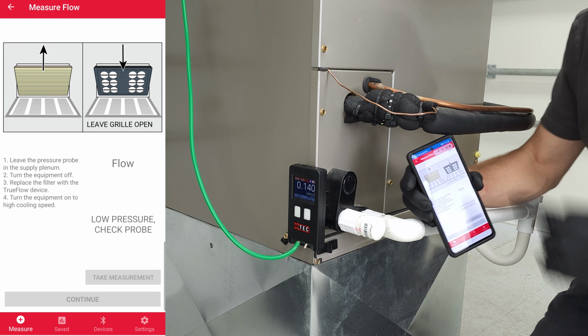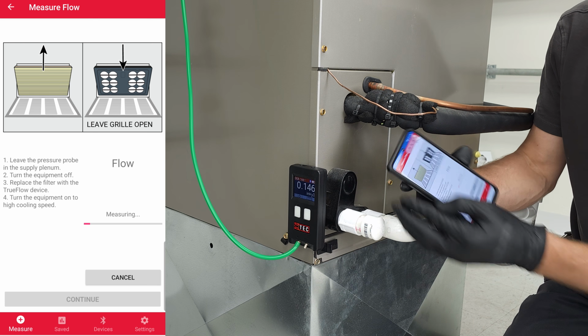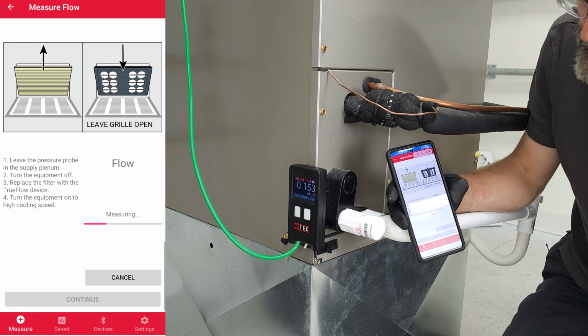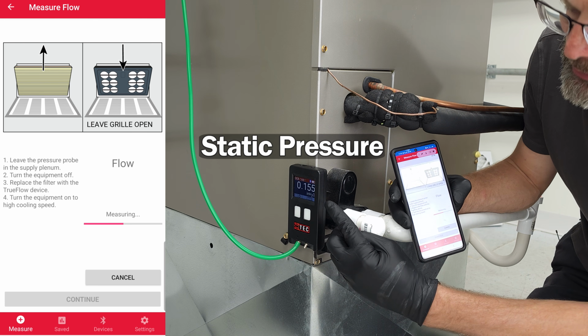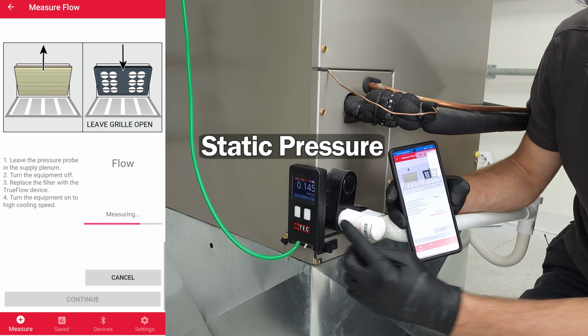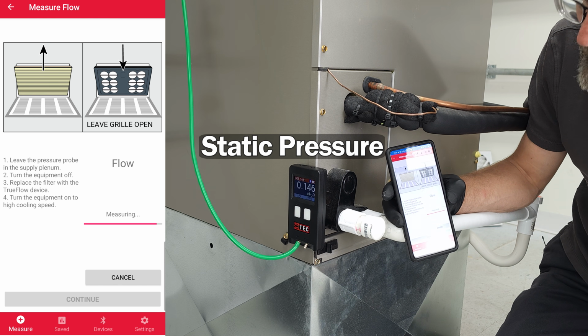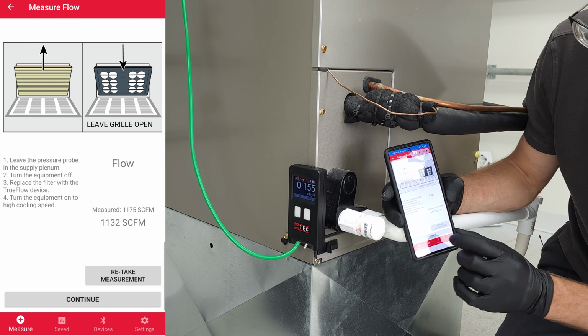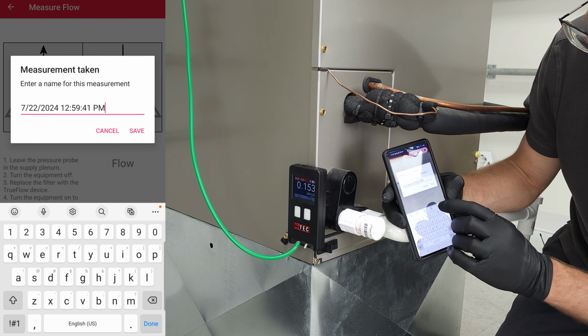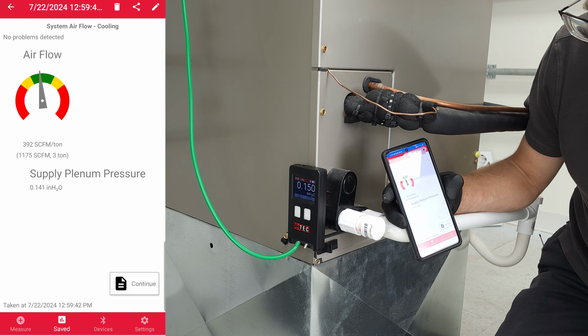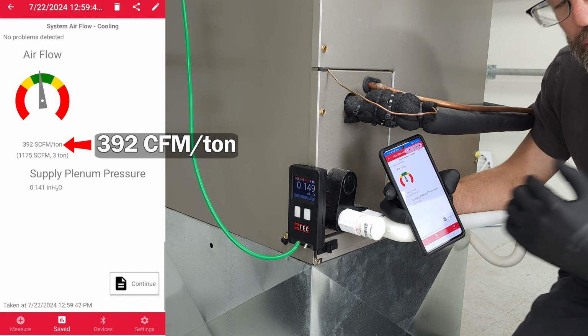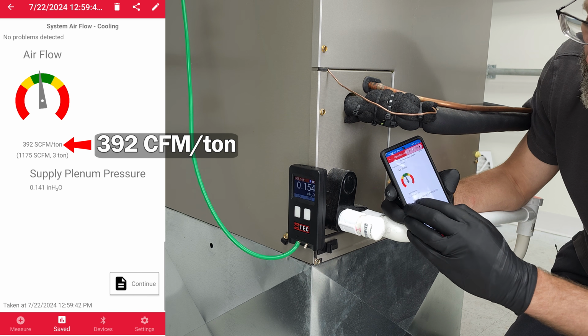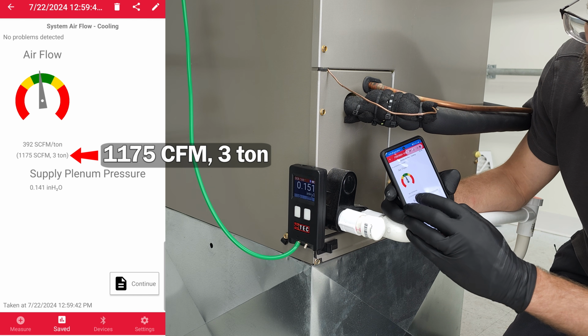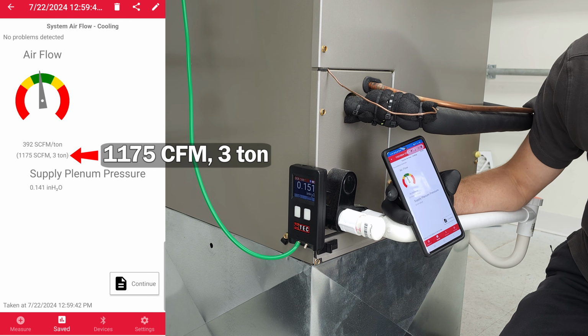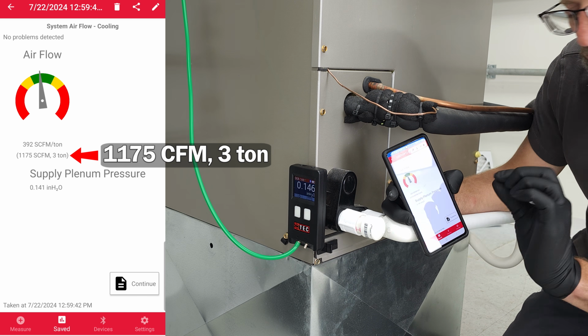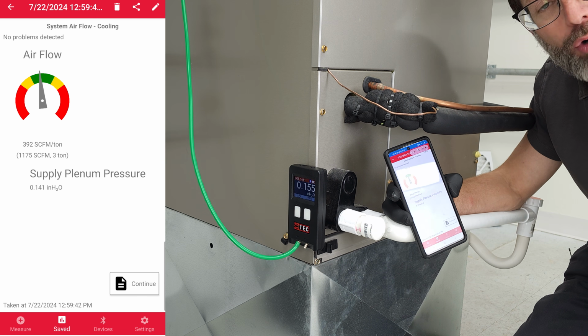Now we're going to switch out our filter with our TrueFlow grid. We're going to take our measurement now. So this static pressure measurement is a reference point in order to be able to measure our CFMs through this app. And so continue. We can save this. And it's saying that our airflow is 392 CFMs per ton. So we have 1,175 CFMs for our 3 tons. And so we are good. So if anything, we're just slightly low. I mean, we're right on there, right on 400 CFMs.